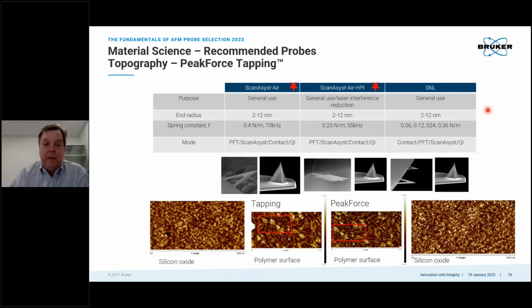For ScanAsyst topography, there are 2 primary probes I use. The ScanAsyst-Air, which apparently a lot of you are using also, which is good. It's a great probe, nice and sharp, and low spring constant, 0.4 newtons per meter. And then the ScanAsyst-Air-HPI. So HPI is a paddle shaped probe. So it's kind of narrow and then has a wider end to it for better laser reflection. So if you're getting optical light spillover with the ScanAsyst-Air, then you could use the HPI probe.